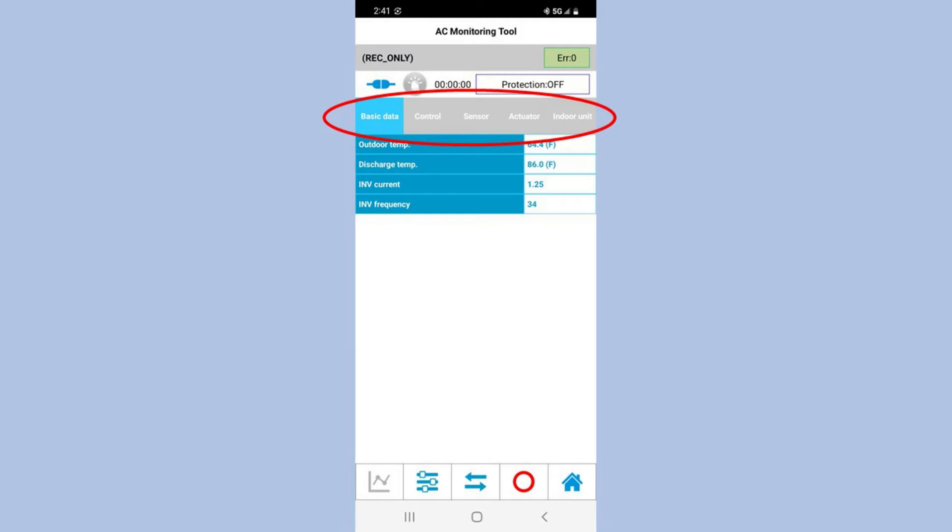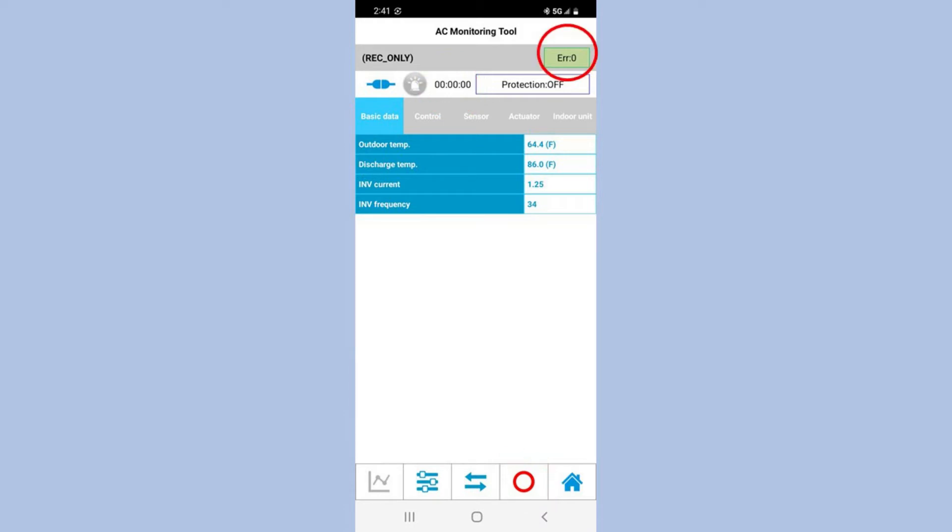When we do open it up, this is what we're gonna see. A few items of note: if we do record, it's gonna be that bottom red button there for record, and we'll also have the clock up top which is showing us to record and the record button will light up as we see coming up here. Any errors with the system will appear in the top right. Protection modes also will appear. Again, a protection mode is not an error. If you've done the classes, you know protection mode just gonna limit the frequency of a compressor for various reasons.